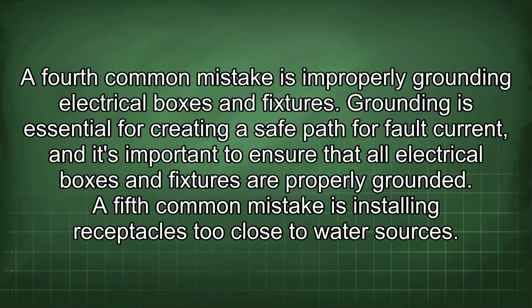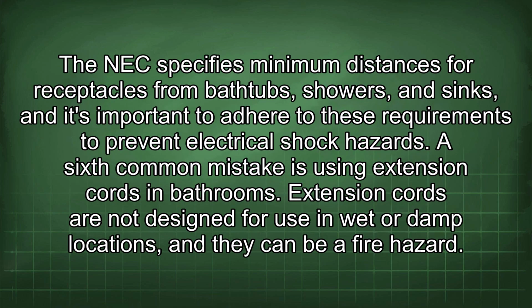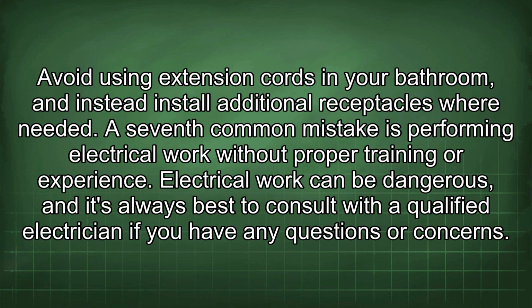A fifth common mistake is installing receptacles too close to water sources. The NEC specifies minimum distances for receptacles from bathtubs, showers, and sinks, and it's important to adhere to these requirements to prevent electrical shock hazards. A sixth common mistake is using extension cords in bathrooms. Extension cords are not designed for use in wet or damp locations, and they can be a fire hazard. Avoid using extension cords in your bathroom, and instead install additional receptacles where needed.